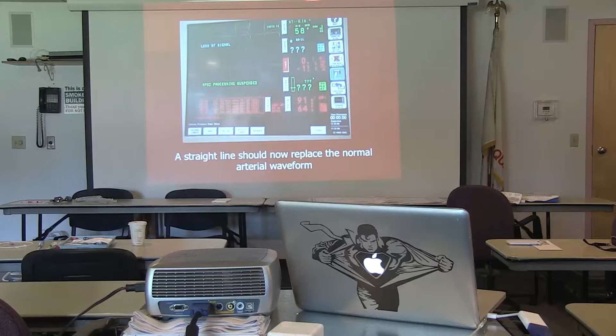What we're going to do is hit the 0 button, and then that's going to give us our basis. Okay? Then you're going to turn the stopcock back off to the air. You're going to connect the fluid with the blood in the artery, right? So the stopcock is up so that the pathway is open now. Okay? Replace the dead end cap and make sure the waveform returned to baseline. And there's your waveform. And you can see that dicrotic notch.